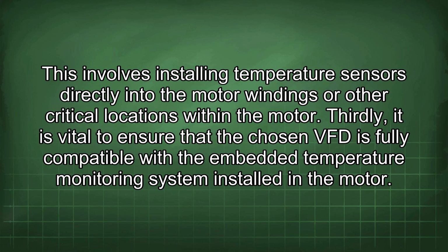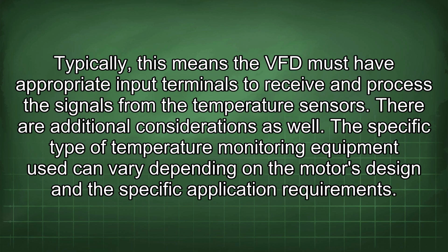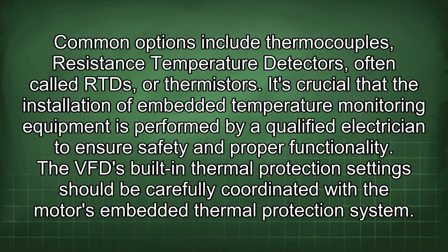Thirdly, it is vital to ensure that the chosen VFD is fully compatible with the embedded temperature monitoring system installed in the motor. Typically, this means the VFD must have appropriate input terminals to receive and process the signals from the temperature sensors. There are additional considerations as well. The specific type of temperature monitoring equipment used can vary depending on the motor's design and the specific application requirements. Common options include thermocouples, resistance temperature detectors, often called RTD, or thermistors.